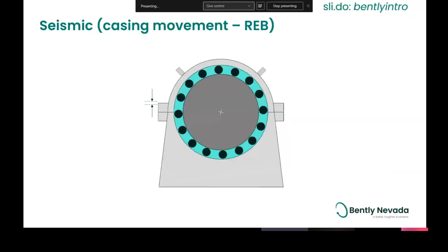And one more scenario I want to mention for those that are, particularly in the power gen business, or anybody with a large steam turbine generator where things are very massive but still using sleeve bearings. There we have something that we call a shaft absolute measurement. So in this scenario, the shaft is moving relative to the bearing housing, but the bearing housing is moving as well. So just one technology alone, whether it be just proximity probes or just velometers, is only going to tell you part of the picture.